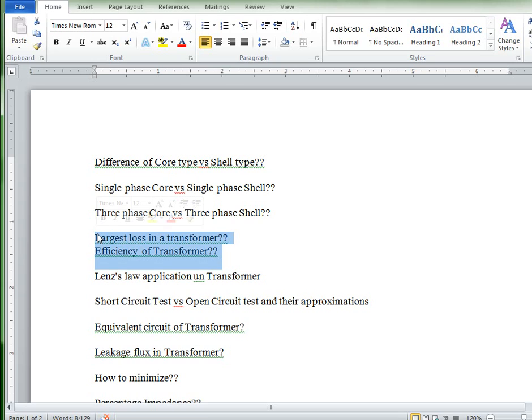Remember one thing, as this course progresses, you will find out that it's a trade-off. Either you keep iron losses small and the copper losses will increase, or if you keep the copper losses small, the iron losses will increase. It's a trade-off over there. But whenever you are designing a transformer, the largest loss is always copper loss, and that is dependent upon the current flowing inside the winding. That is the copper losses, the I square R losses, which I am talking about. So the resistance of the winding is very important.